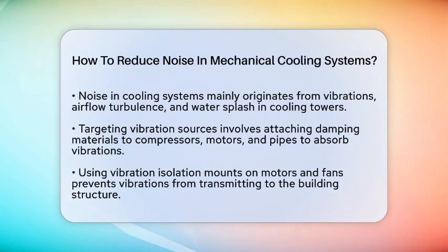Noise in cooling systems mainly comes from three sources: vibrations from compressors, motors, and fans, airflow turbulence that creates aerodynamic noise, and water splashing or spraying in cooling towers. The goal is to target these noise sources carefully while keeping the cooling performance high.